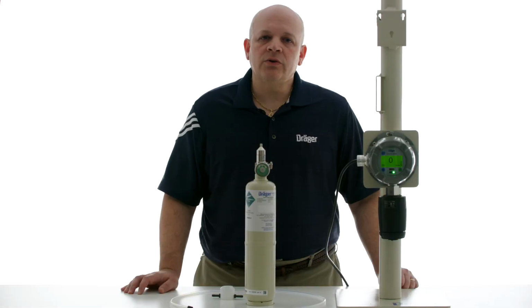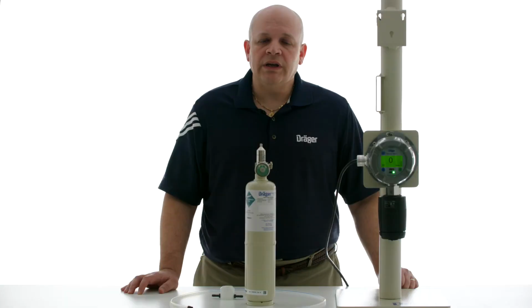Once the detector goes into calibration mode, it will transmit a signal below 4 milliamps. If the detector is connected to a controller such as the Regard 7000, the controller will recognize that the detector is in maintenance mode and will not set off any faults or alarms. If you are using any other controller, please be sure that it understands signals below 4 milliamps.